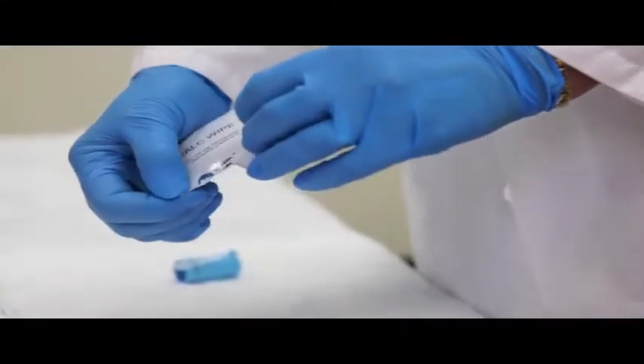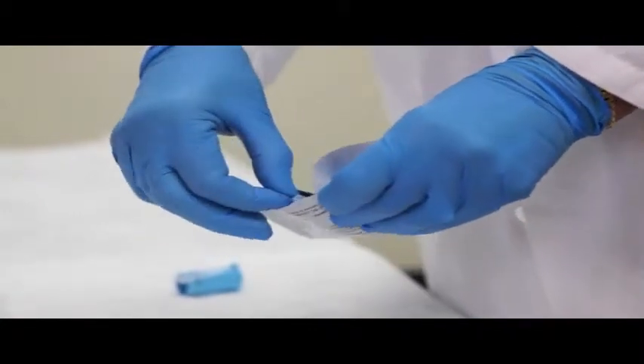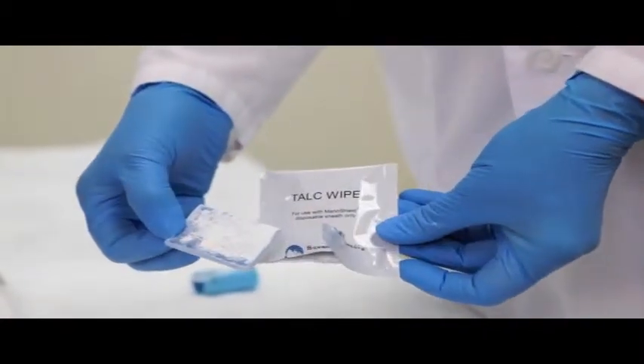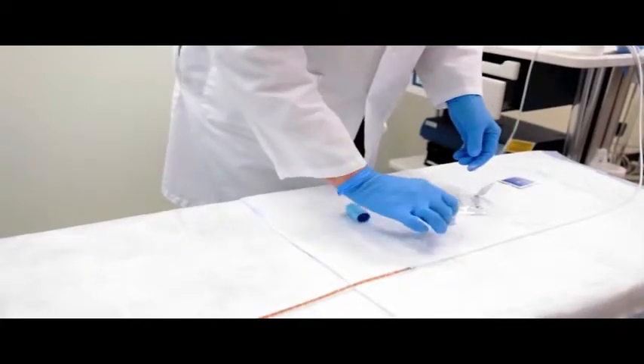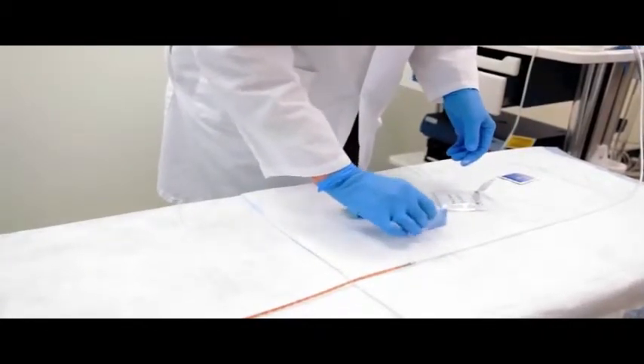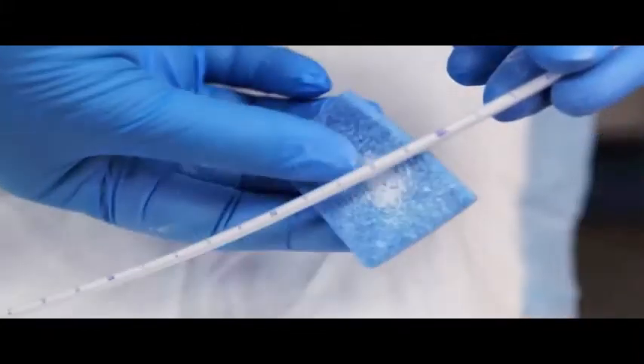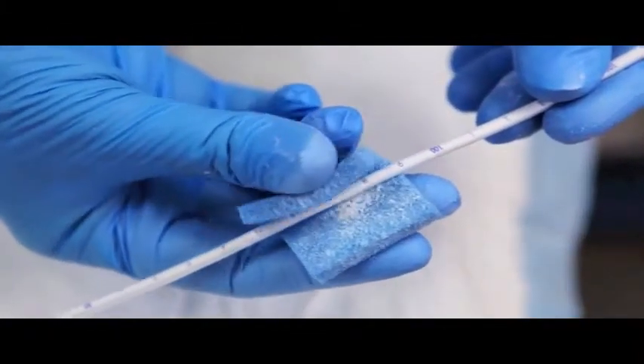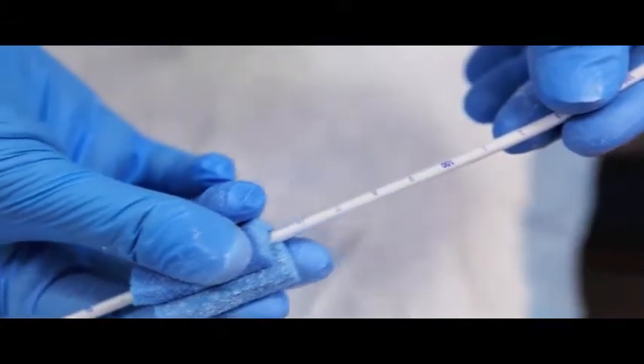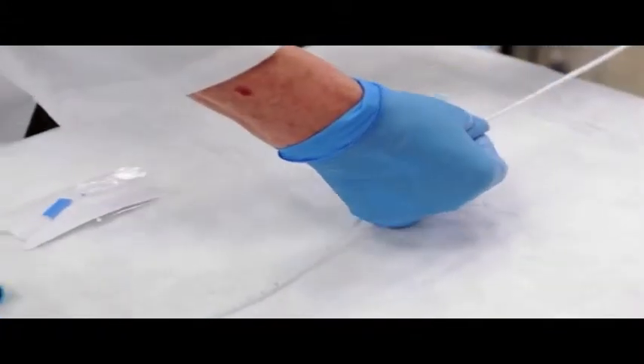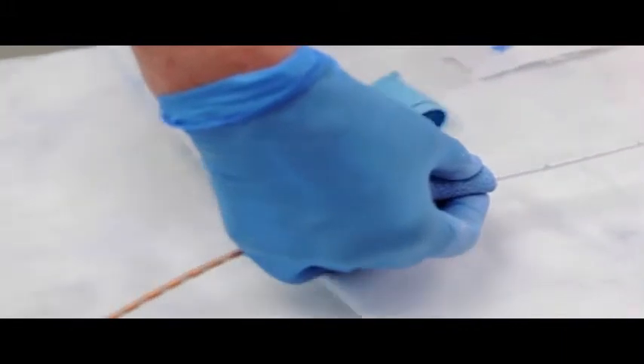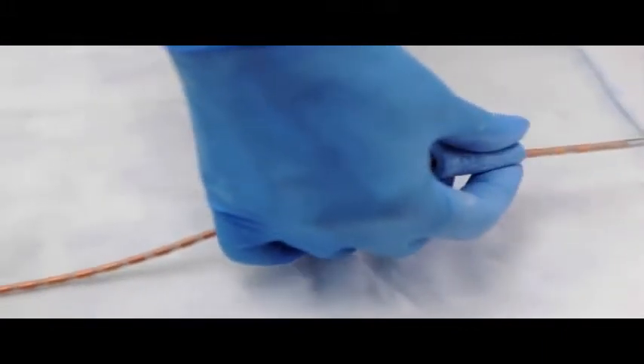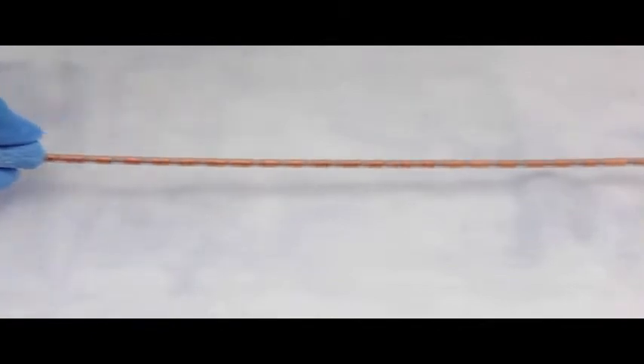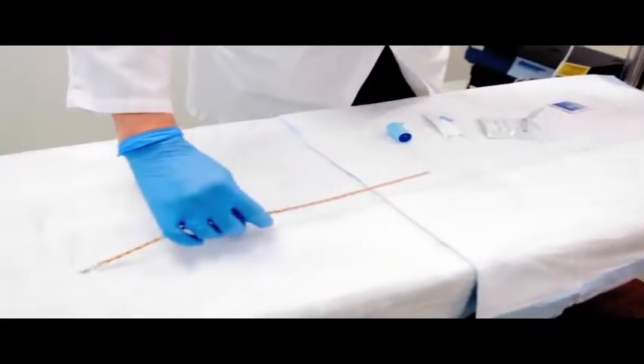readings. A thin, even coating of the supplied talc lubricates the catheter's surface and facilitates application of the Manoshield to the catheter. With the catheter on a clean, toweled, flat surface, gently fold the supplied talc-infused sponge over and around the Manoscan catheter near the 100 centimeter mark. Slide the talc sponge with light, even pressure down the length of the catheter to the tip. Do not allow the catheter to touch the floor or other surfaces. The goal is to apply a light, even coating of talc along the entire length of the catheter.